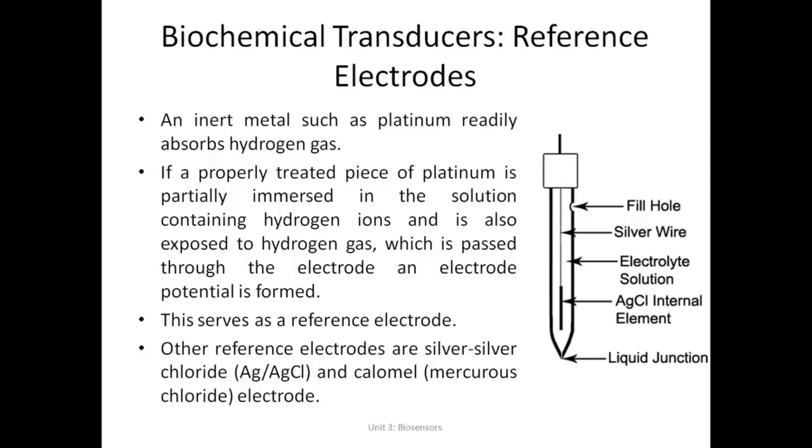The electrode potential for the silver chloride reference electrode depends on the concentration of the KCl. Calomel is actually another name for mercurous chloride, a chemical combination of mercury and chloride ions. The interface between mercury and mercurous chloride generates the electrode potential. By placing the calomel side of the interface in the potassium chloride filling solution, the electrolytic bridge is formed to the sample solution from which the measurement is to be made.